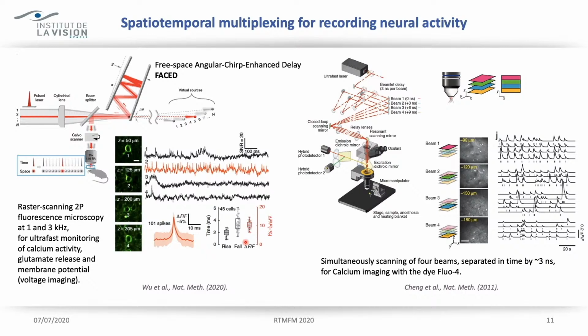Since the fluorescence lifetime is shorter than the repetition periods of pulsed lasers used for two-photon excitation, single pulses can be divided into multiple excitation beams, which can be laterally or axially displaced to illuminate the different sample regions at different, almost simultaneous times. By accurate synchronization of the excitation beamlets with a detector using high-speed electronics, sequentially excited fluorescent signals can be demultiplexed.